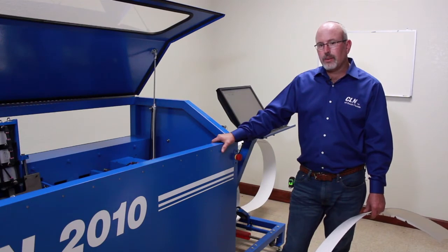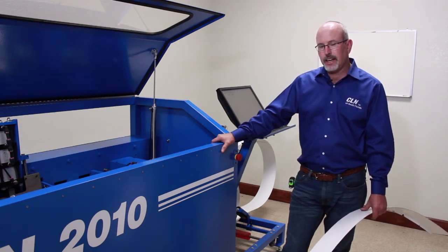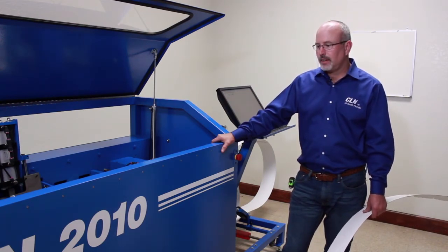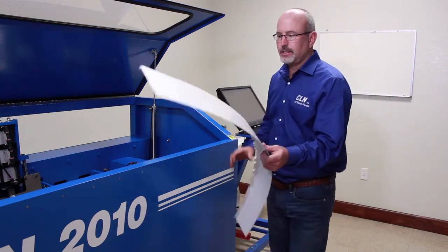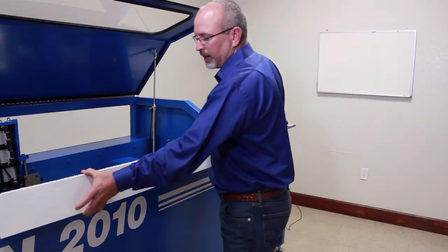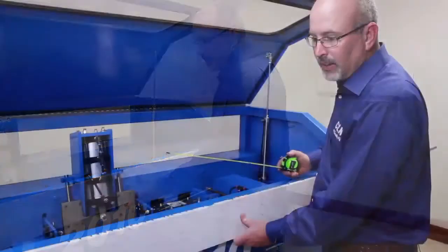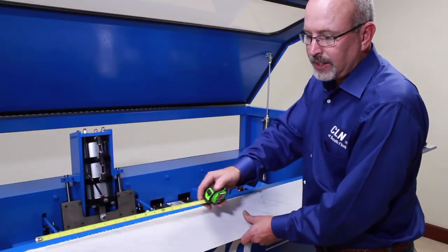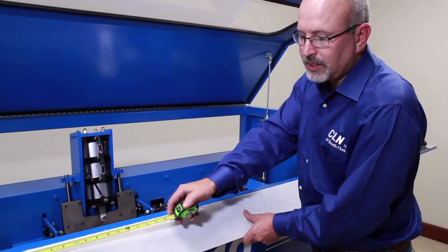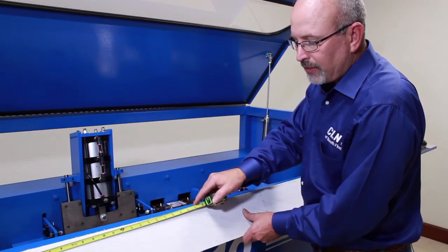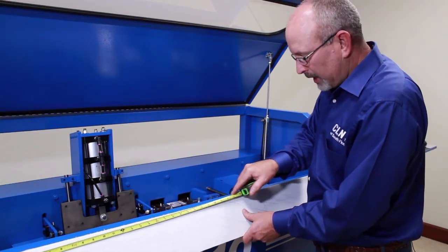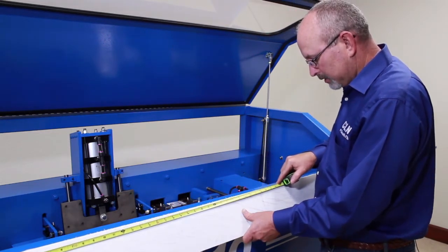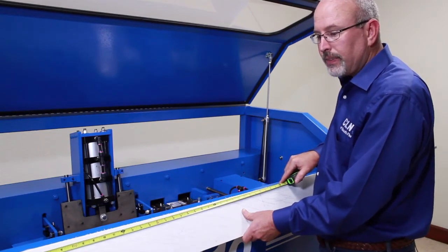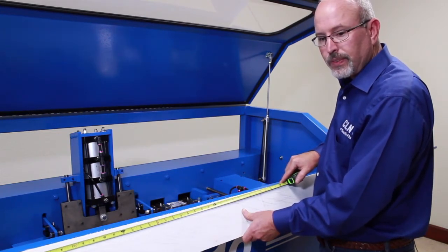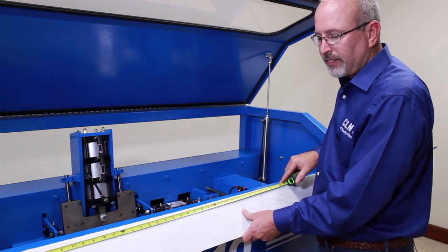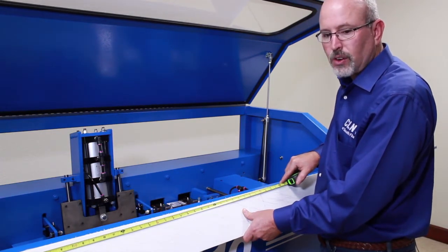Now we're going to talk a little bit about how to test for calibration errors. I want to show you a quick way to see if your machine is running correctly. The easiest way to do it is take a tape measure and hook it onto the edge of your return. Now, every 12 inches, you should have a 30-degree notch. That notch is there as a relief for the flanger. It has nothing to do with the DXF file. It's just something the machine does automatically.